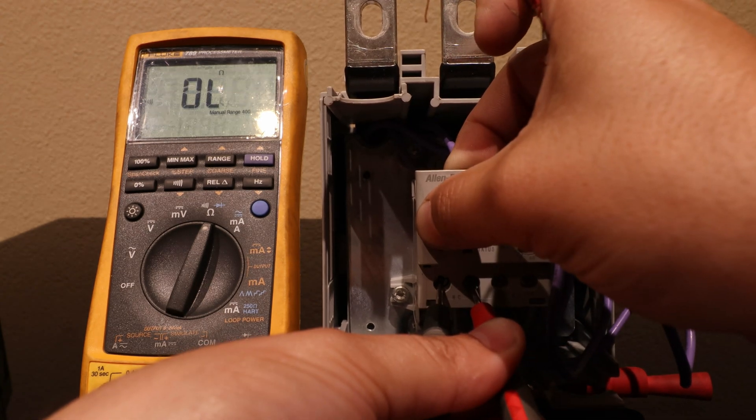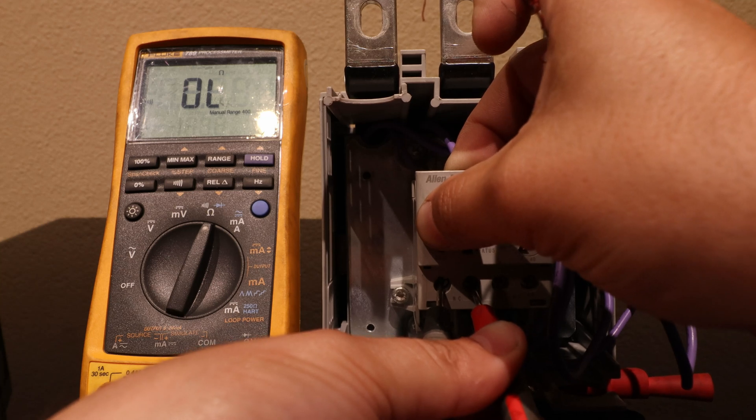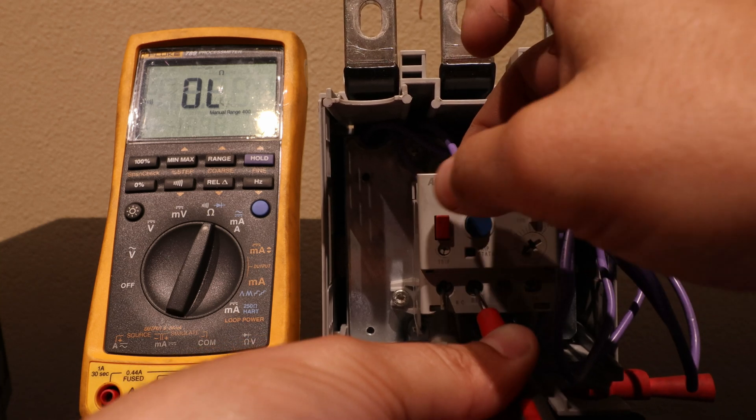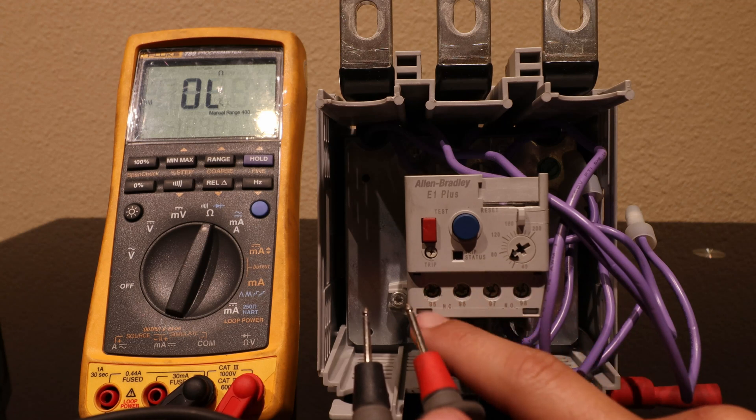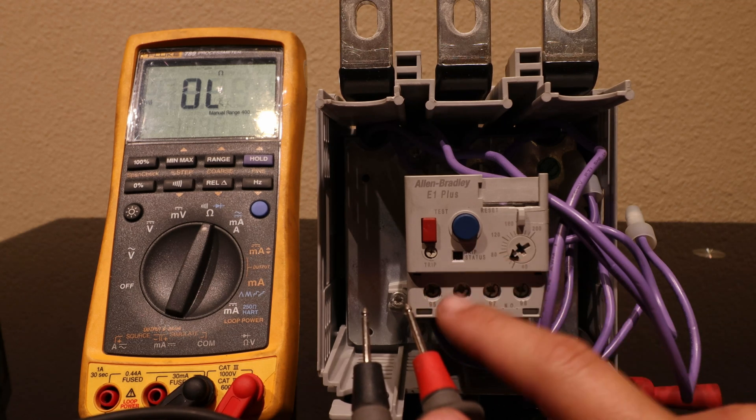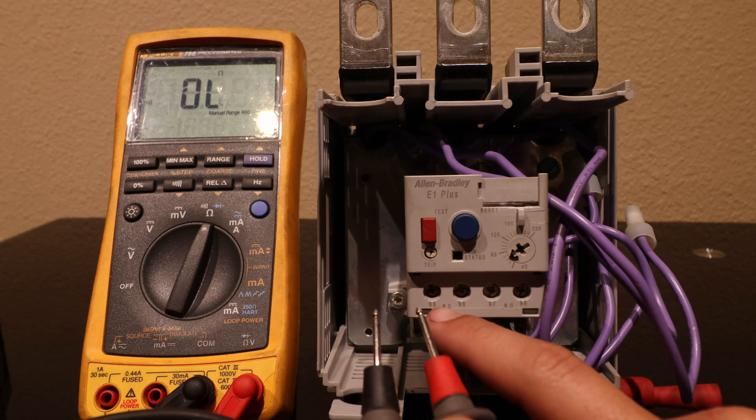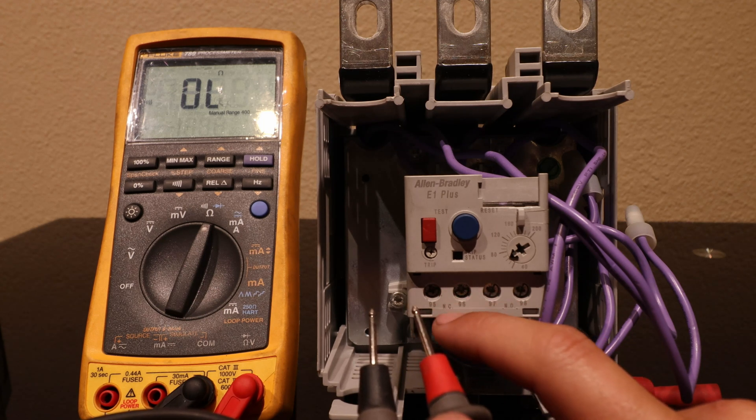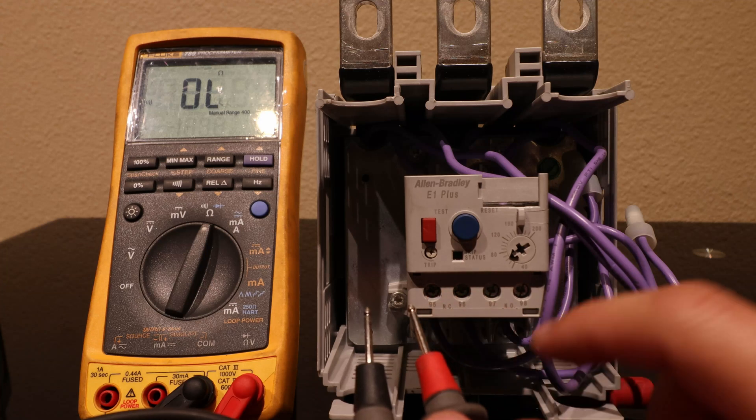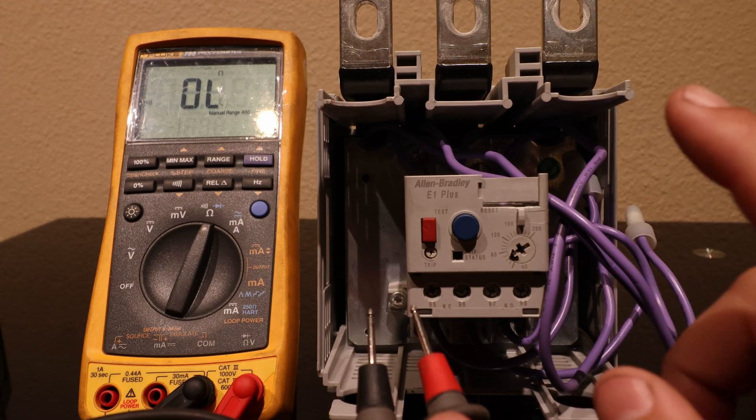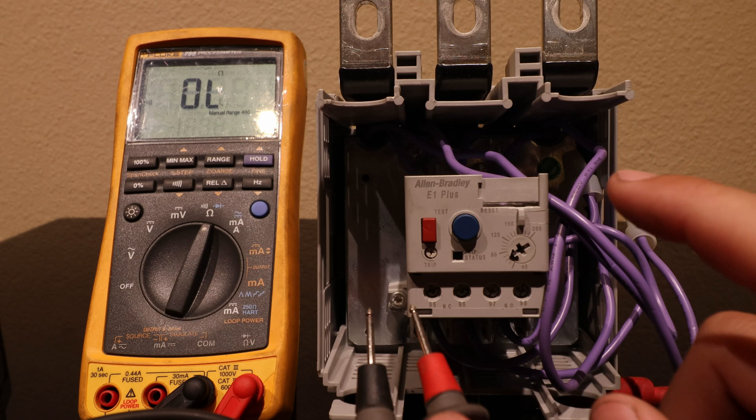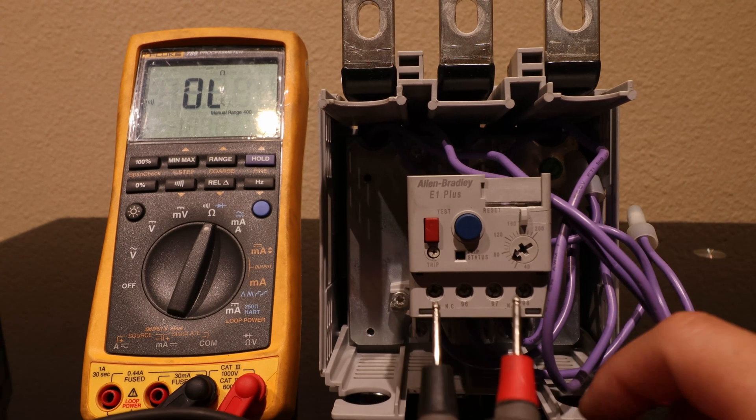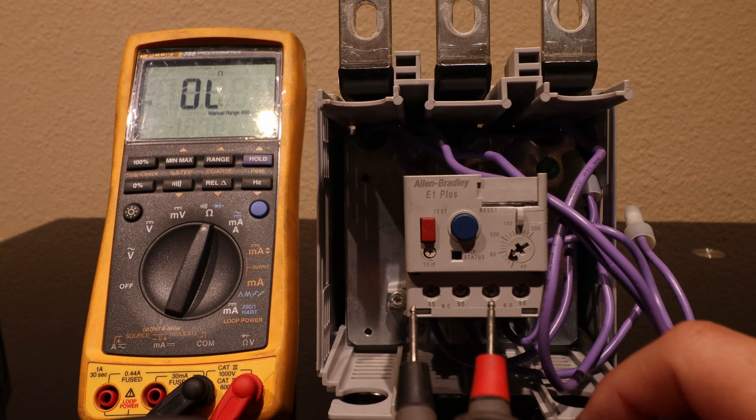This is how the overload relay actually protects the motor from an overcurrent condition. You would either want to wire a normally closed loop here through your controller that's looking for a normally closed loop so that when the overload trips and opens these normally closed contacts it will release power to the contactor and save your motor or prevent a thermal incident.